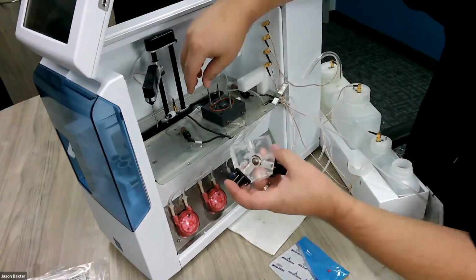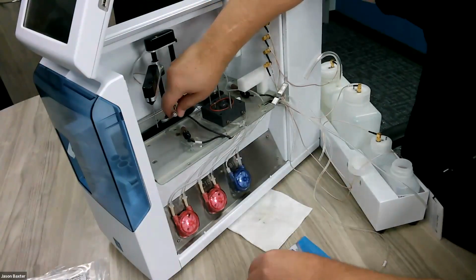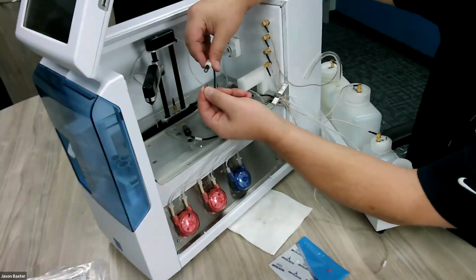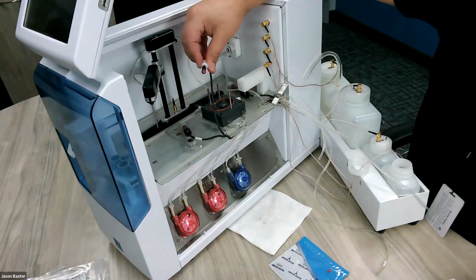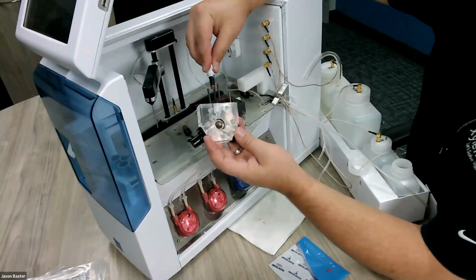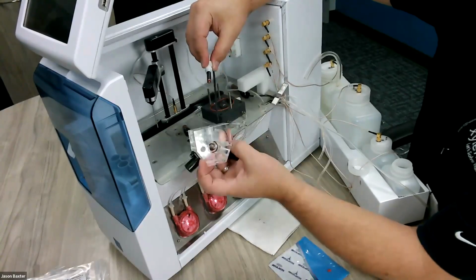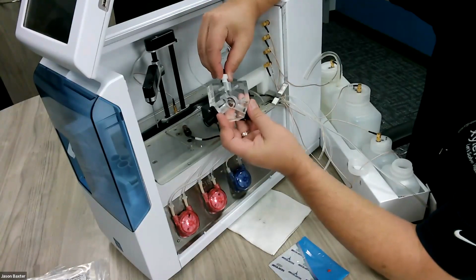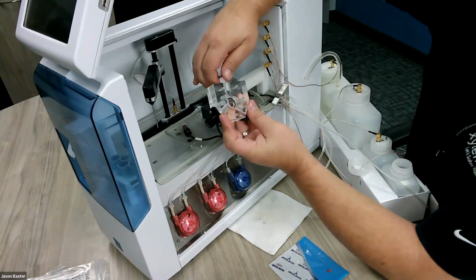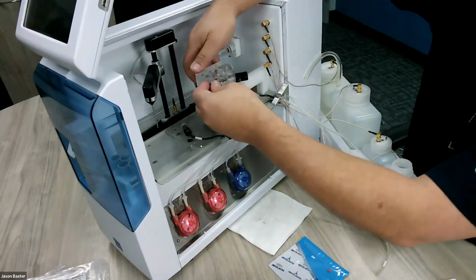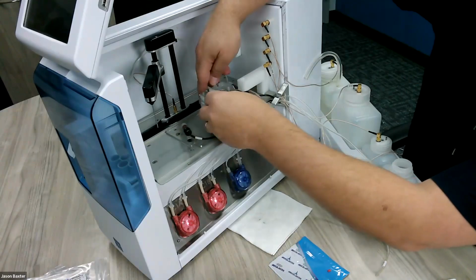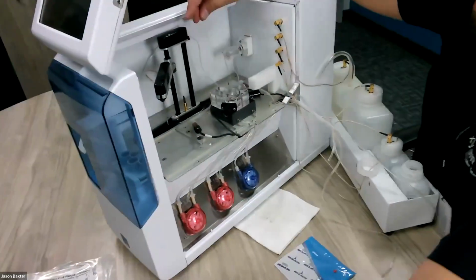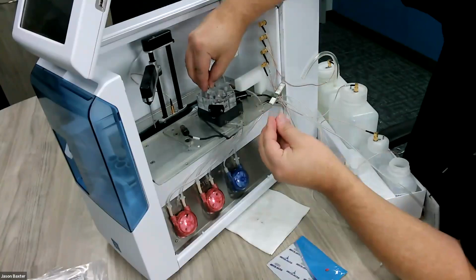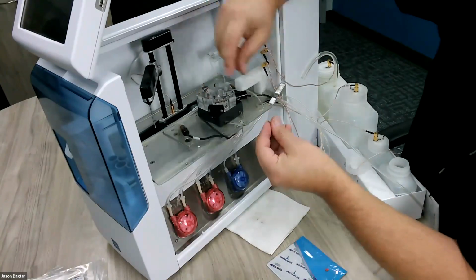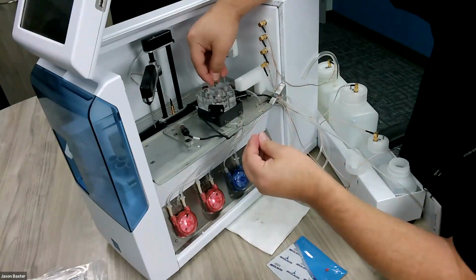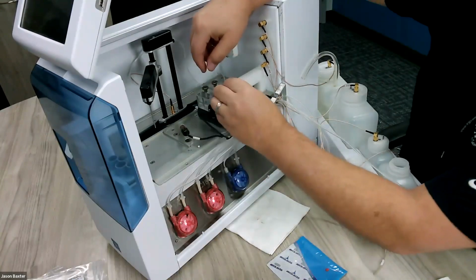Take your sample chamber. Oh, I almost forgot it, just like Ben was advising earlier. Please remember this small O-ring on your temperature sensor. It's a very easy one to miss, very easy one to forget. So just set it on the end of your temperature sensor. Reinstall temperature. Nest sample chamber back into place. Find your 3 thumb screws. 1, 2, 3.